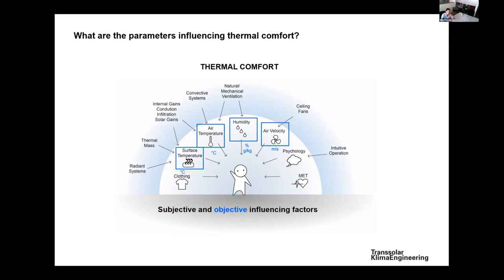Then you also have objective climate parameters: surface temperature, air temperature, humidity, and air speed. These four parameters have an objective impact on the way you feel and perceive your comfort. Two of these — air temperature and surface temperature — can be combined, and we will see later how and why, to make another metric called operative temperature.